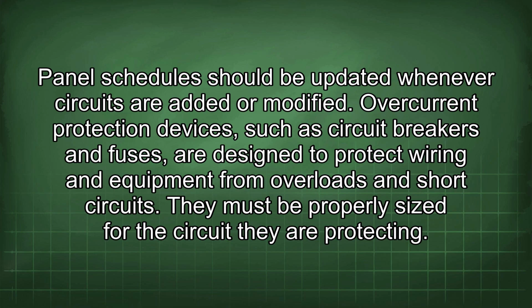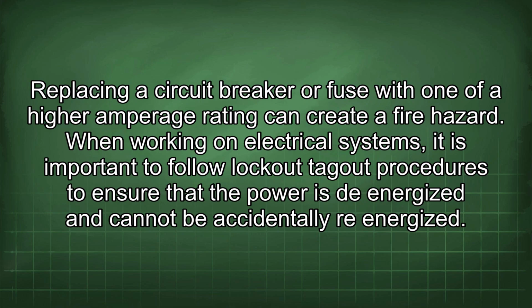Overcurrent protection devices, such as circuit breakers and fuses, are designed to protect wiring and equipment from overloads and short circuits. They must be properly sized for the circuit they are protecting. Replacing a circuit breaker or fuse with one of a higher amperage rating can create a fire hazard.